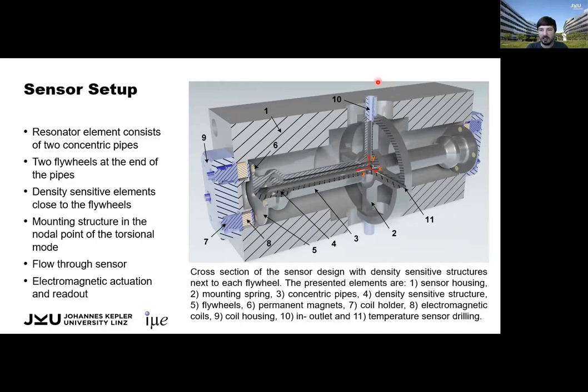The sensor is designed as a through-flow sensor. The fluid flows in through inlet 10, then in the space between the two pipes on the left side, through the inner pipe on the right side, then again in the space between the pipes back to the middle and out of the outlet.